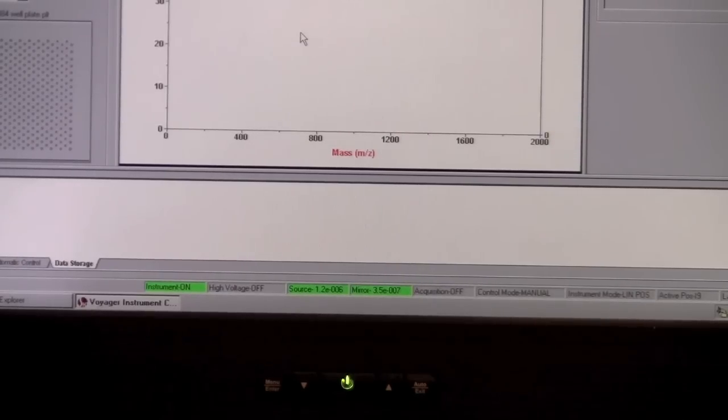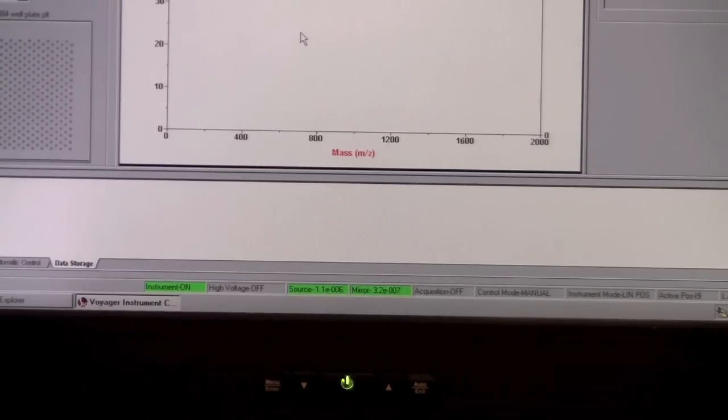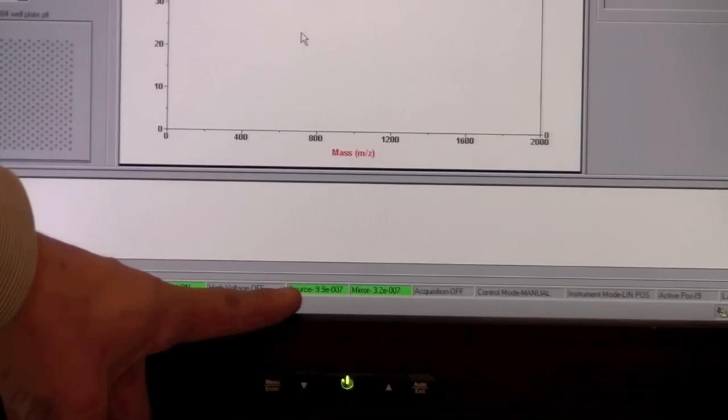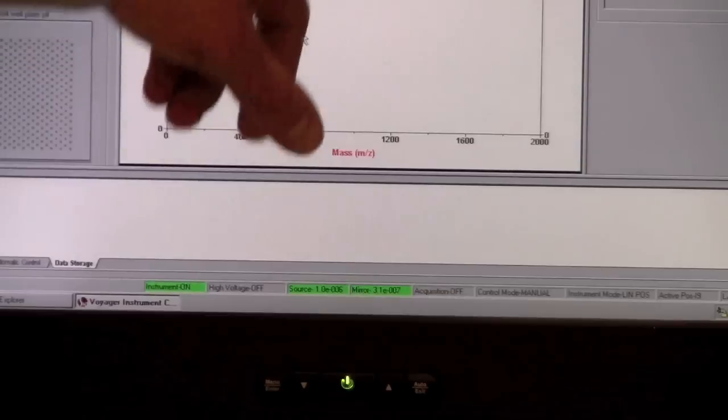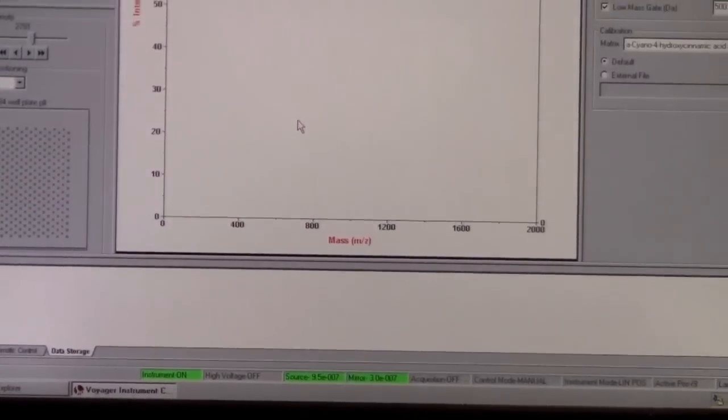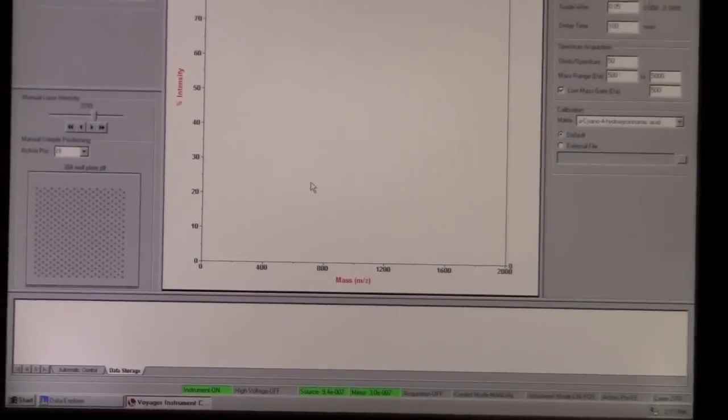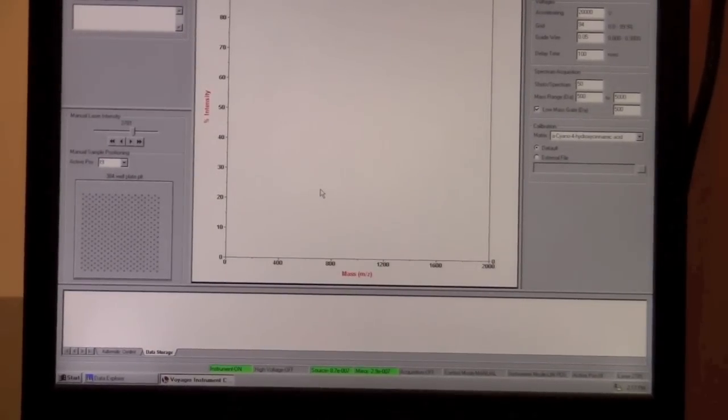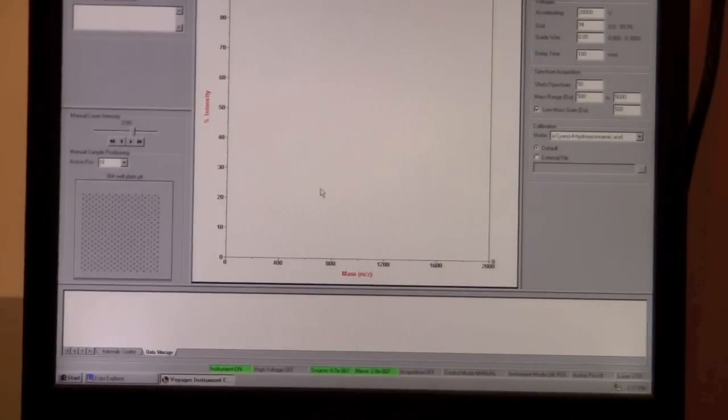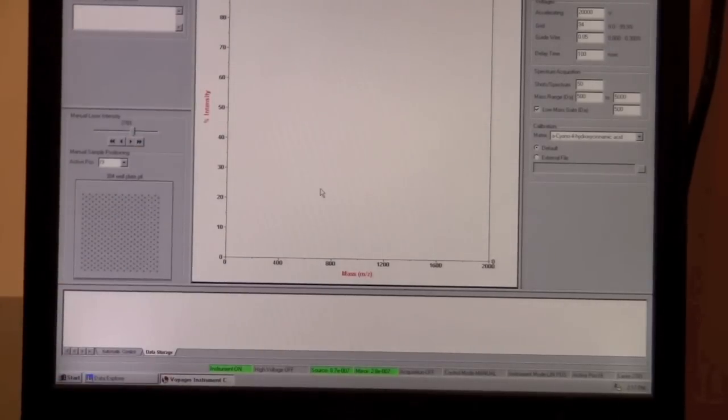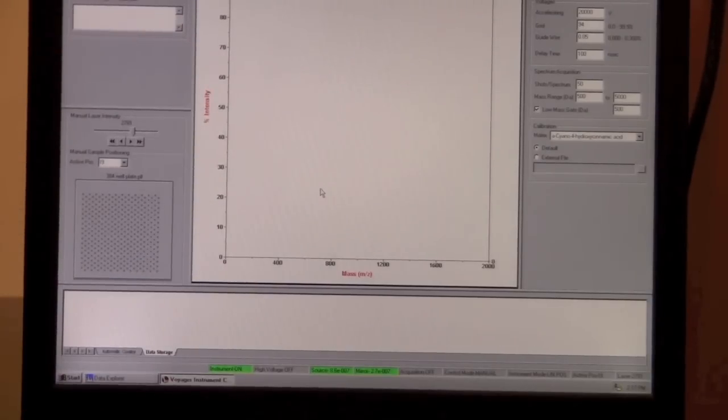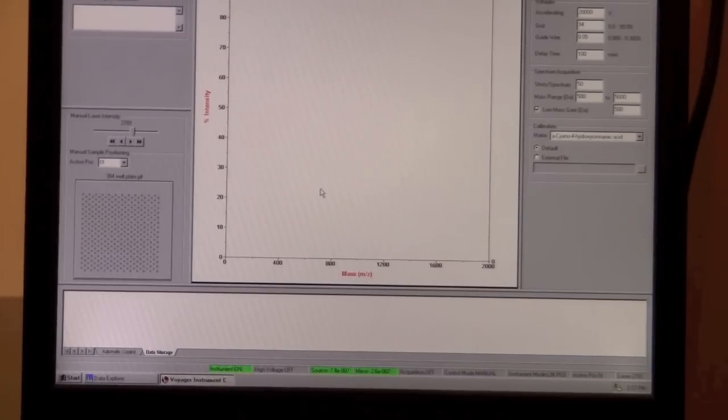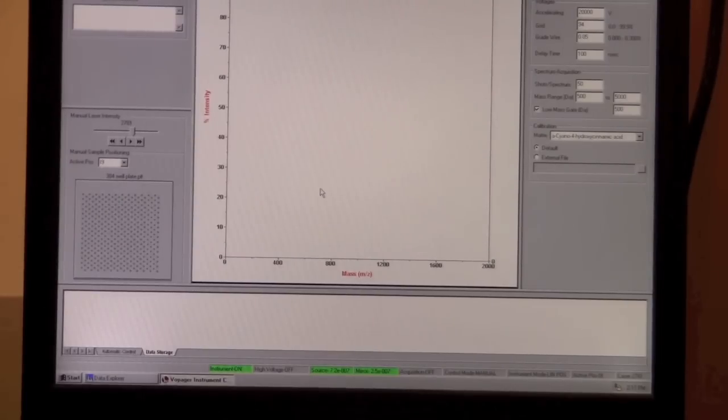If your plate has too much solvent on it, or if the system is wet for any reason, it may take longer than the instrument expects for it to pump down, in which case this may be in the yellow or red, and it may pop up a window saying that the pressure is too high and that it's shut down. If that's the case, don't worry. All you need to do is wait about a minute for the system to pump down further, and then select the reset button. Don't keep repeatedly selecting the reset button. If it doesn't pump down after the first or second time selecting the reset button, then the whole system may shut down. So you want to be patient and let it pump down and try reset one or two times. If you're still having trouble, please contact the Instrument Center staff for help.